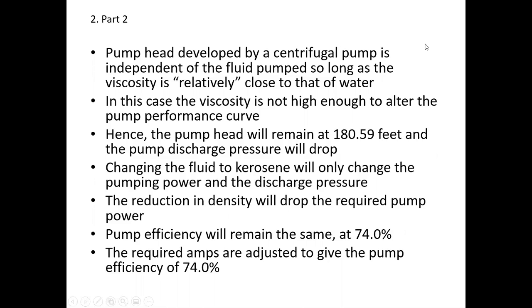The reduction in density will drop the pump power, because you maintain the same volume flow but the fluid doesn't weigh as much, so it doesn't require as much power into the pump. Our point of operation on the pump curve will remain the same. I think it turns out we were at 74% before, so we will still be at 74%. And what you do is adjust the amps on the PSAT analysis for the kerosene in order to have a 74% pump efficiency, again, as we'll see.